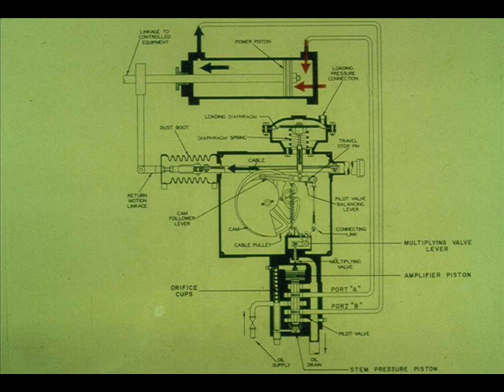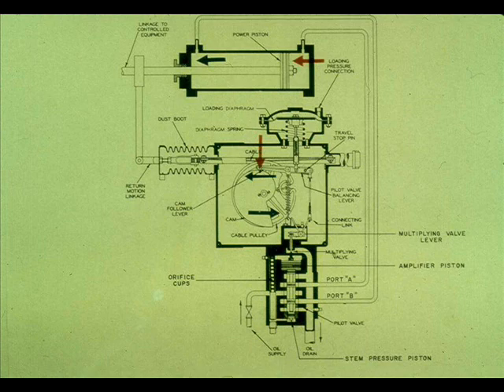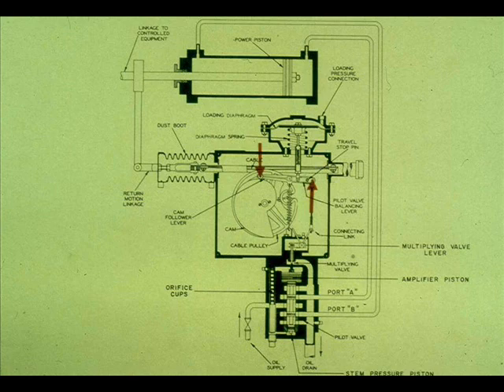The return motion linkage also moves right to left. The cable makes the cam rotate counterclockwise. The cam follower lever lowers. The pilot valve balancing lever rotates. The left end lowers. The right end raises. This repositions the multiplying valve, which repositions the pilot valve. The system is rebalanced.